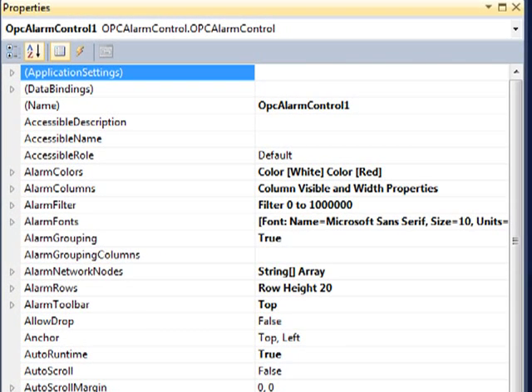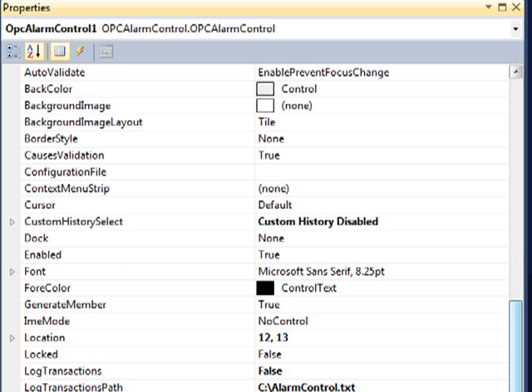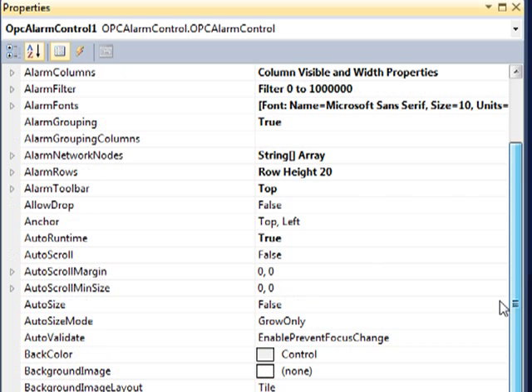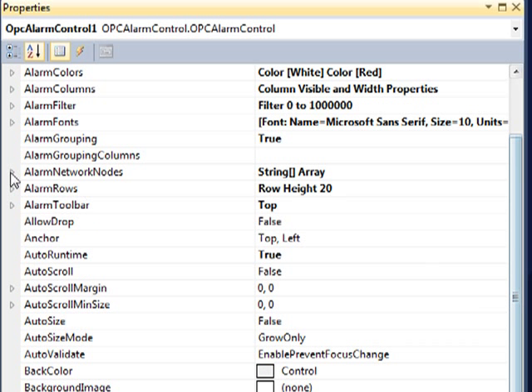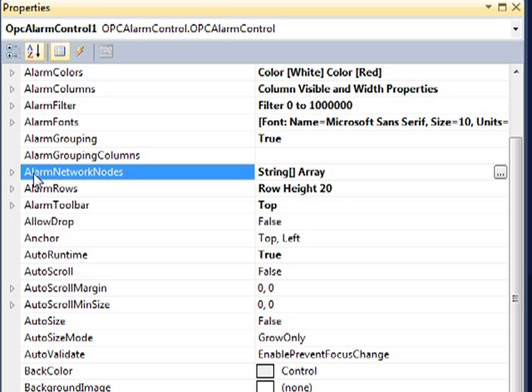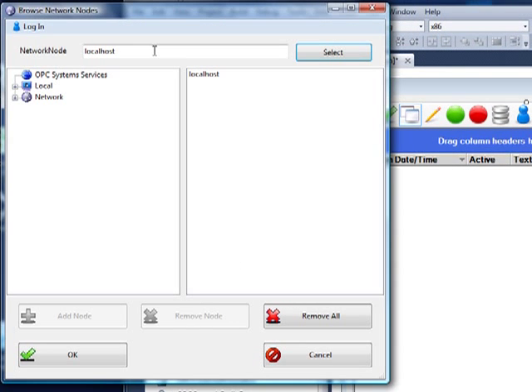The Alarm Control currently is set up to communicate to the local service. If you want it to communicate to a remote service, if you plan to deploy the application on a remote system, you will want to set the Alarm Network Nodes. And here you simply include the IP Address, Network Node Name, or Registered Domain Name.